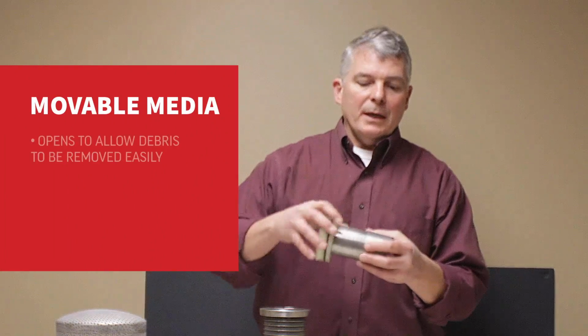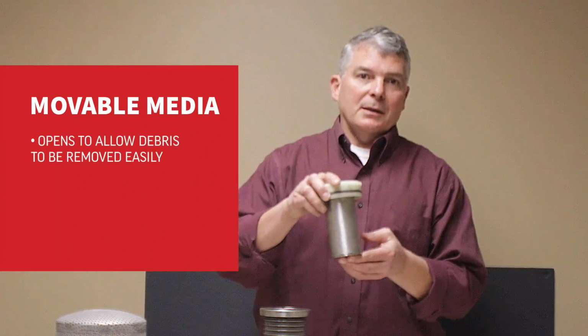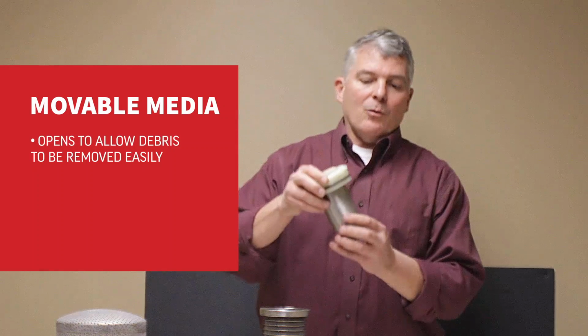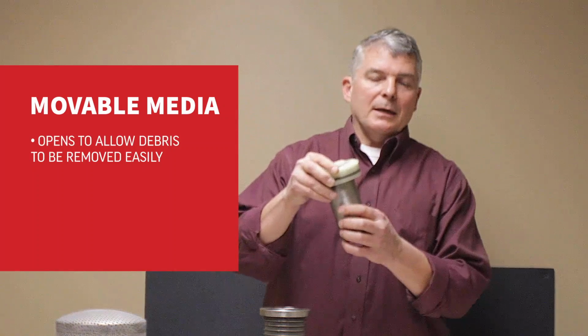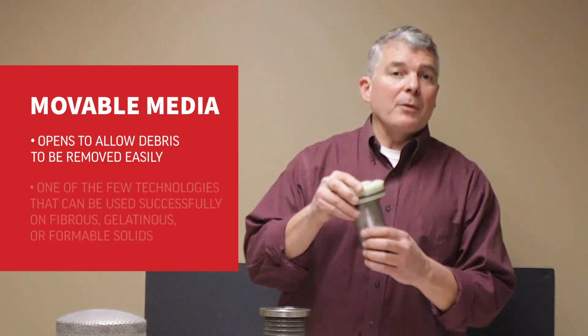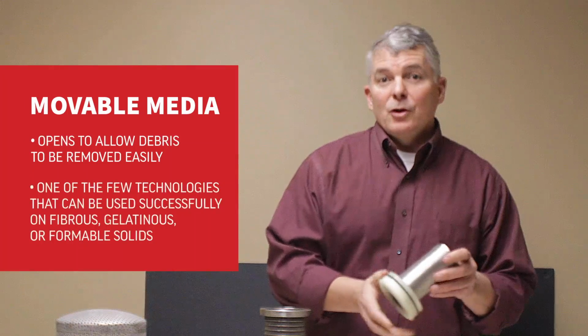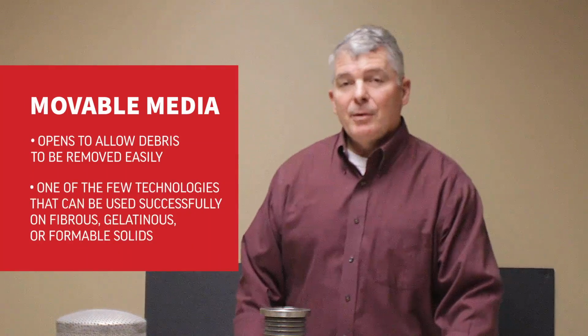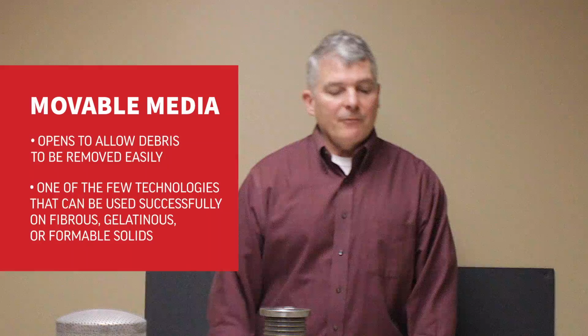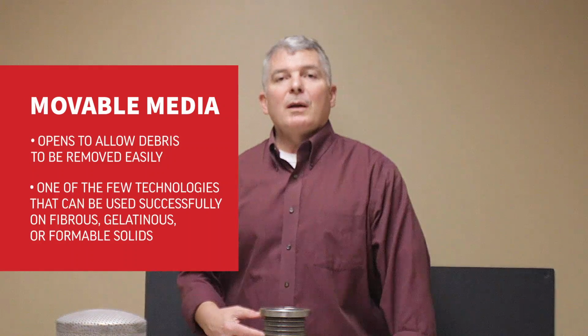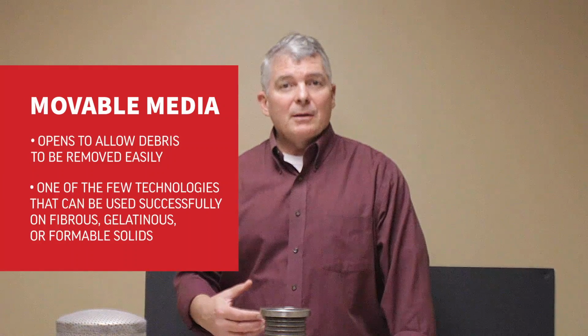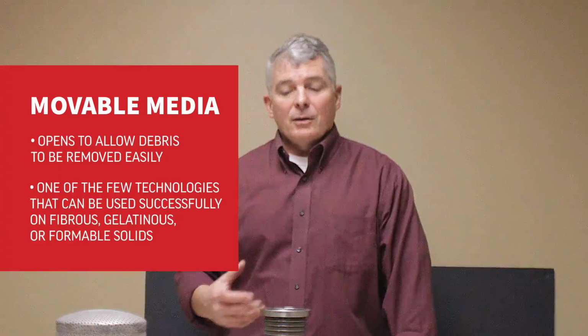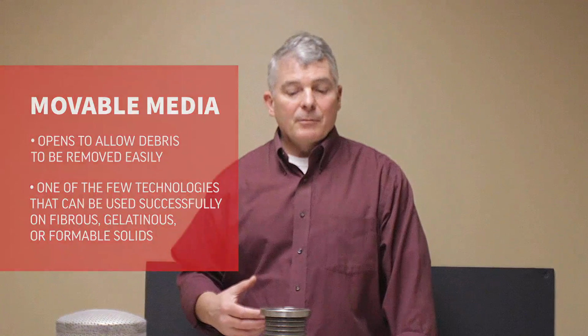We have a movable media. So this coil media during process is in a compressed mode. In backwash, it opens and allows debris to be removed very readily. This is one of the few cleanable technologies that can be used very successfully on fibrous medias as well as gelatinous deformable solids that typically would blind other types of cleanable or self-cleaning medias.